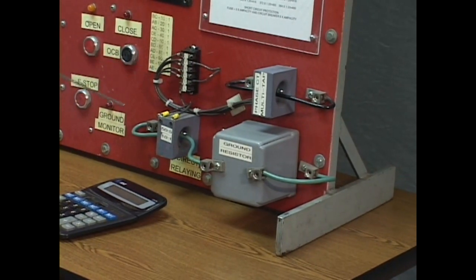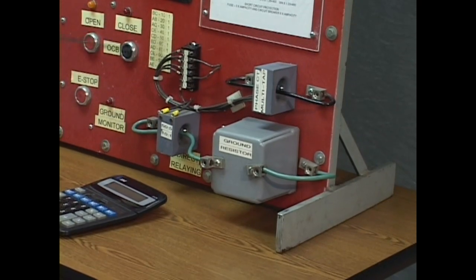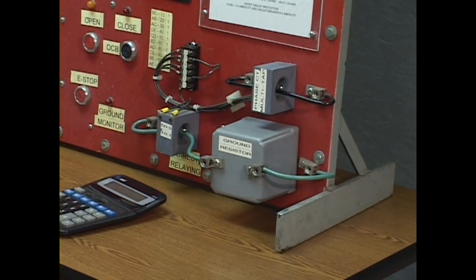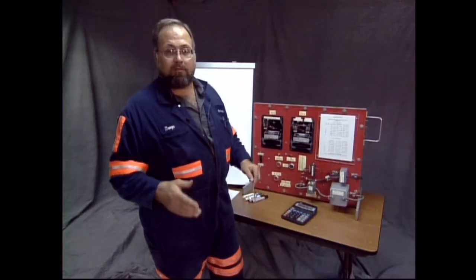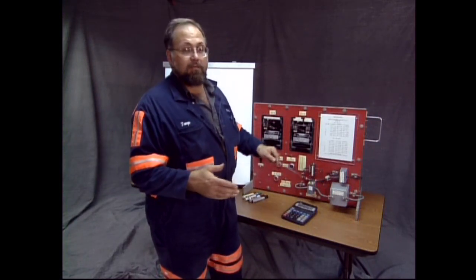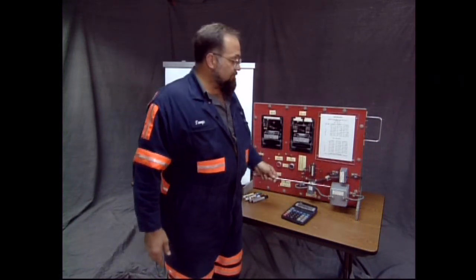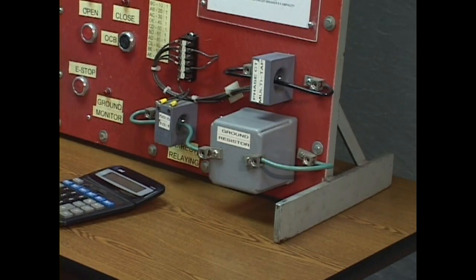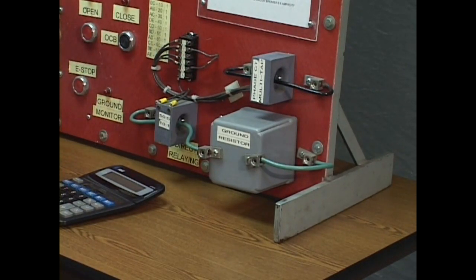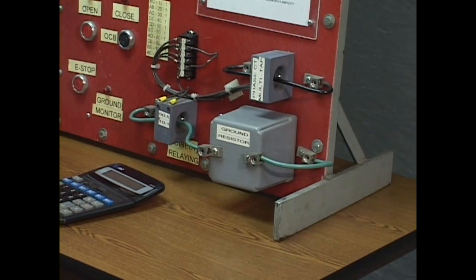The ground resistor is an electric machine. Now, it doesn't appear to be a machine like you would think of something that's got moving parts, that will wobble or shake or do something. It doesn't move. It's static. It doesn't have any moving parts. But it converts any electricity that's on the ground conductor to thermal energy. It's an electric machine. It turns electricity into heat. And you size the ground resistor with its ohmic value and its current rating to accommodate the various voltages that you may encounter in a ground fault.